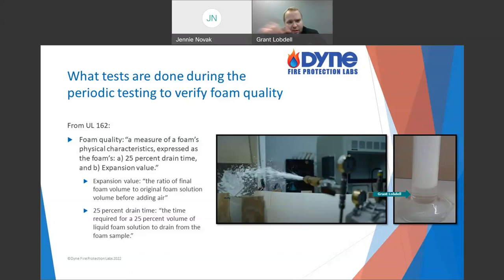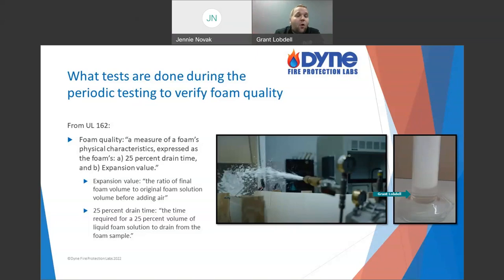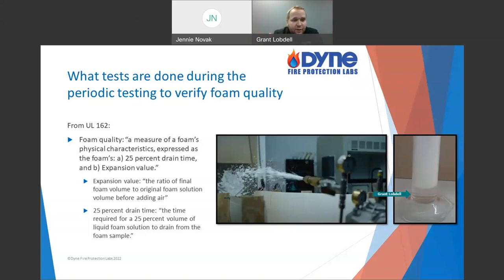Using my crude example: I have 1 milliliter, I shook it up and now it takes up 5 milliliters — a 5-to-1 expansion. I'm going to watch it, and 25% of that 1 milliliter — how long does it take to get back to the bottom? We don't wait for all of it because that would take too long. For low expansion foam we use 25% drain time. For high expansion foams, we typically talk in terms of 50% drain time, since high expansion foams drain a little bit quicker.